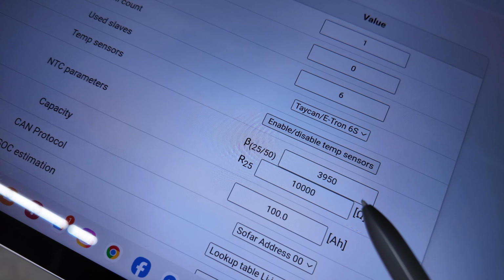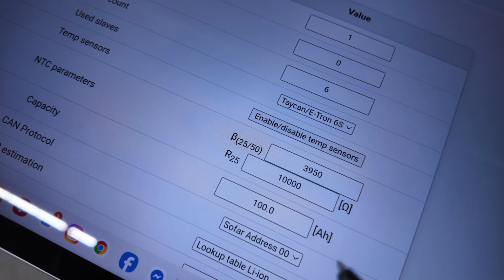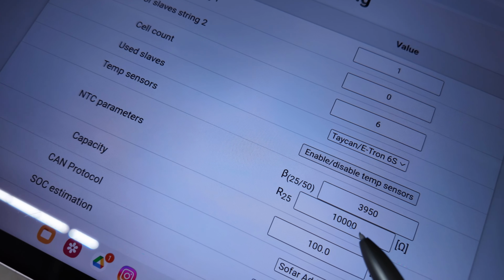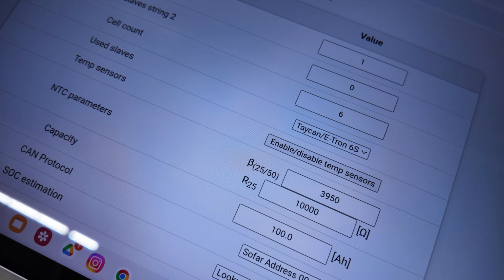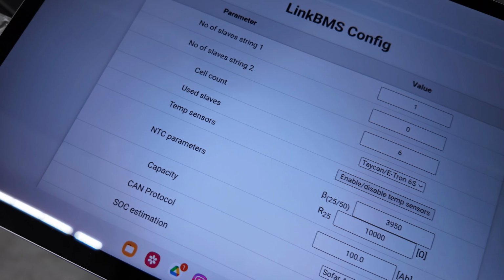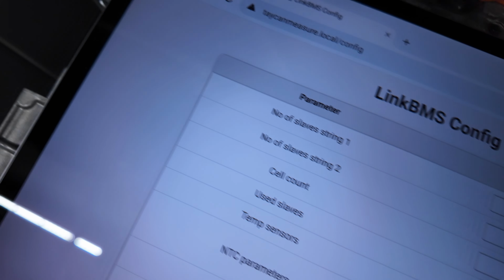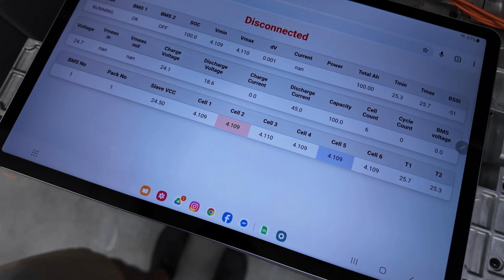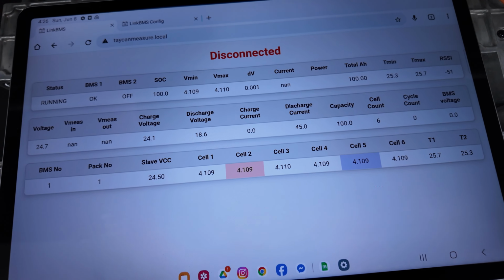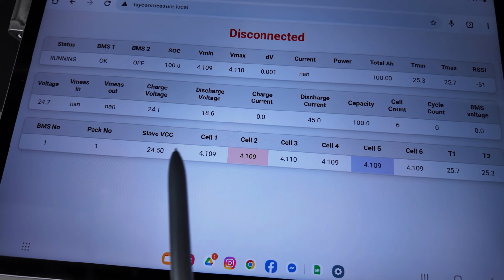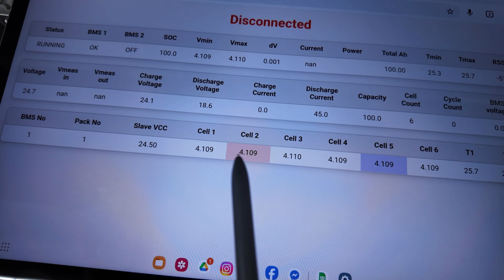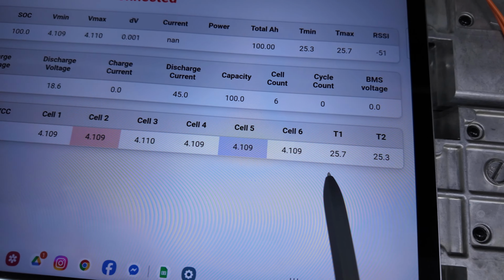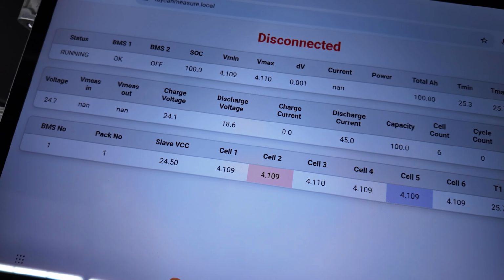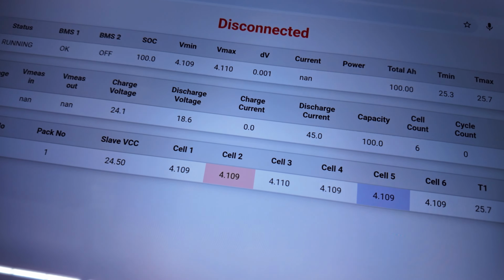In order to make the first measurement, you need to prepare a LinkBMS device configured as 1 unit, 1 string, 1 slave, 6 cells on a 6S slave module. After that, connect directly to, by default, bms.local, and you will have 6 measurements of 6 cells and 6 voltages that you are interested in. Put it directly into the spreadsheet and compare your results across cells, making 2 measurements as I mentioned previously, in order to be sure you don't have any faulty cell inside your battery pack.